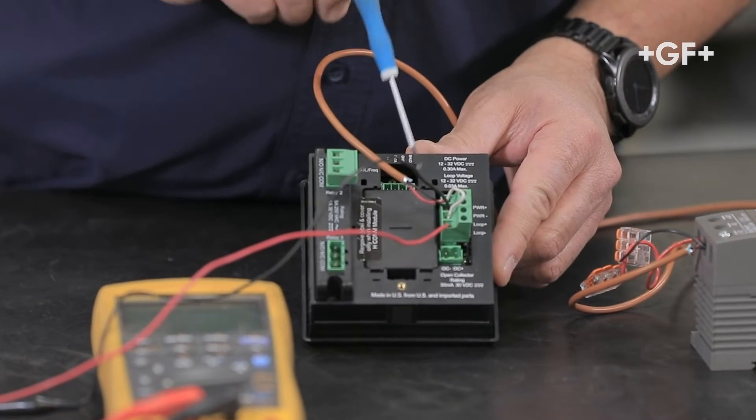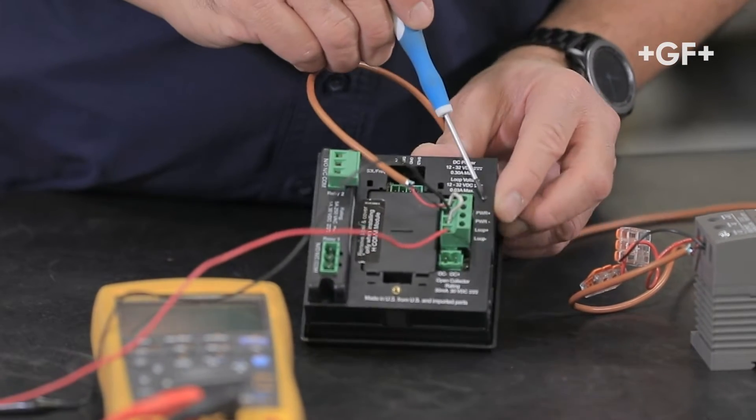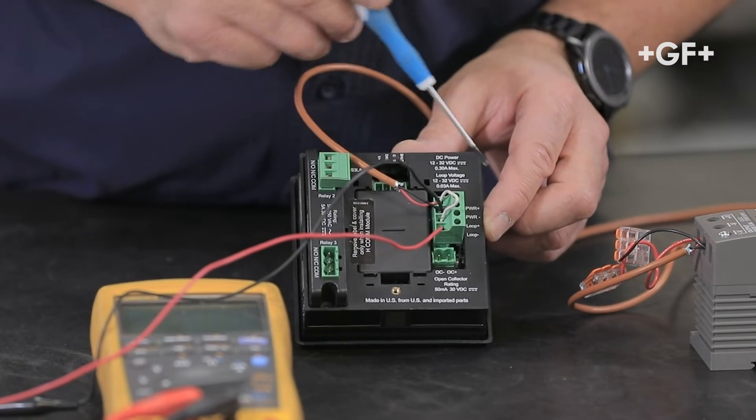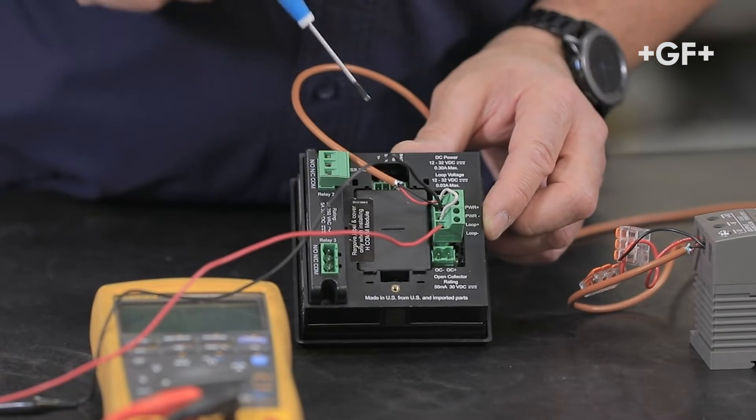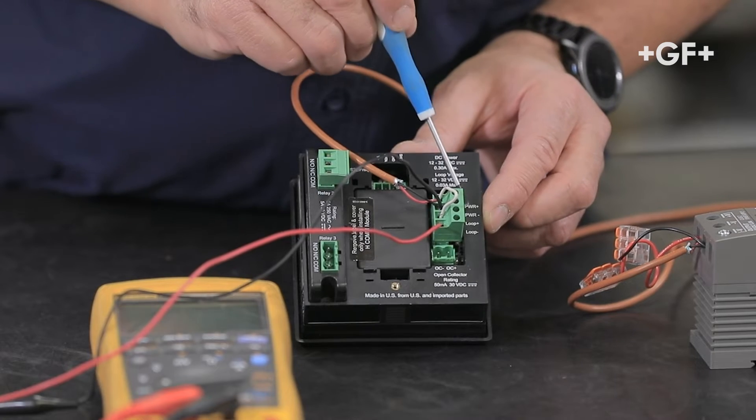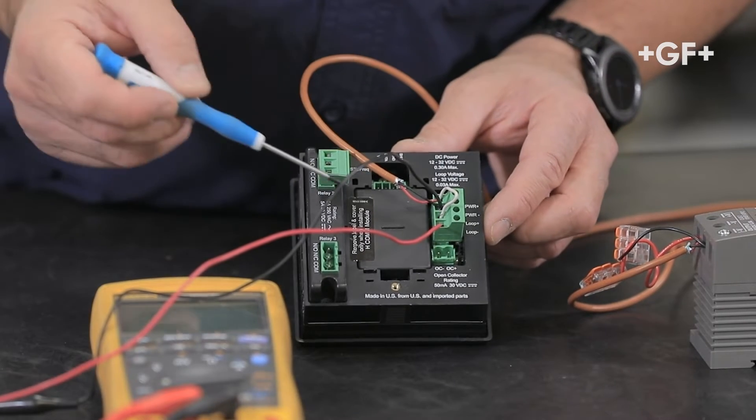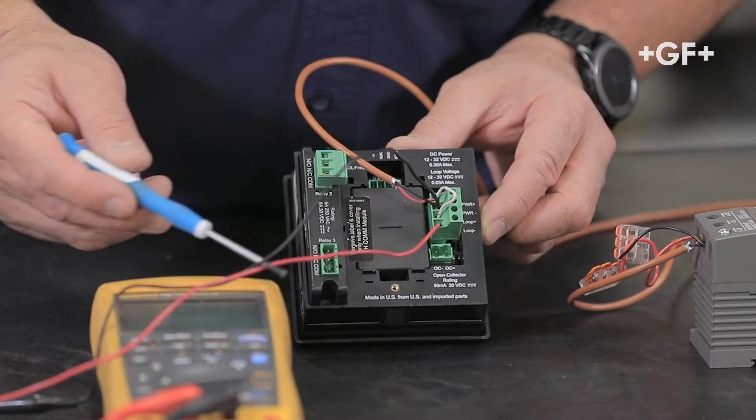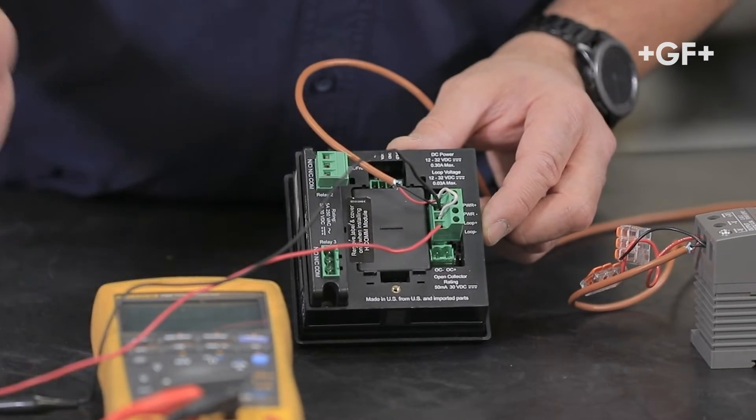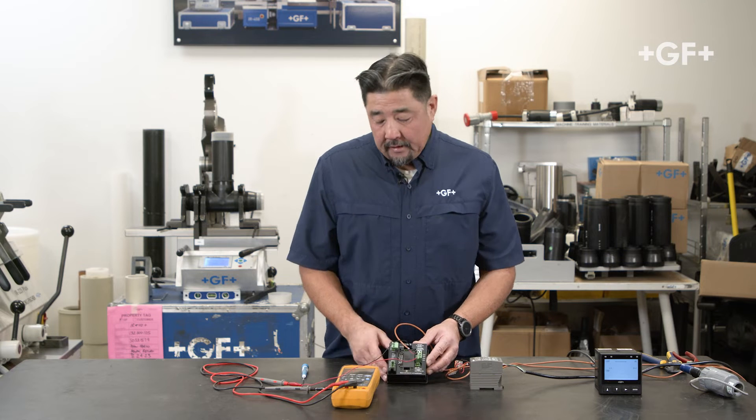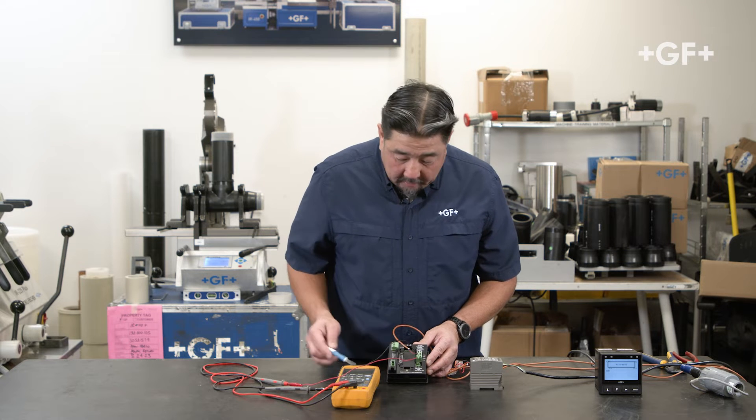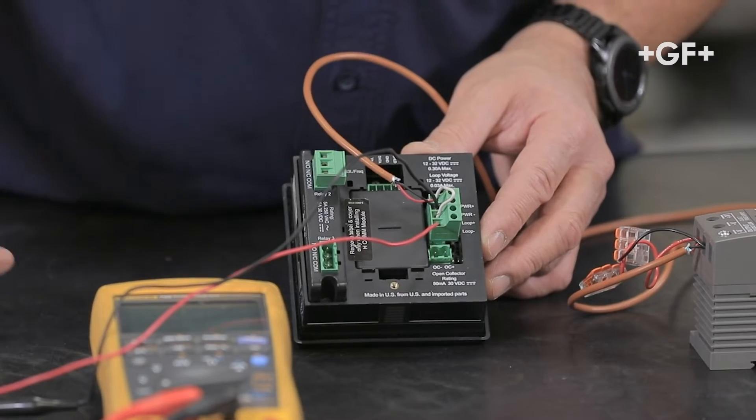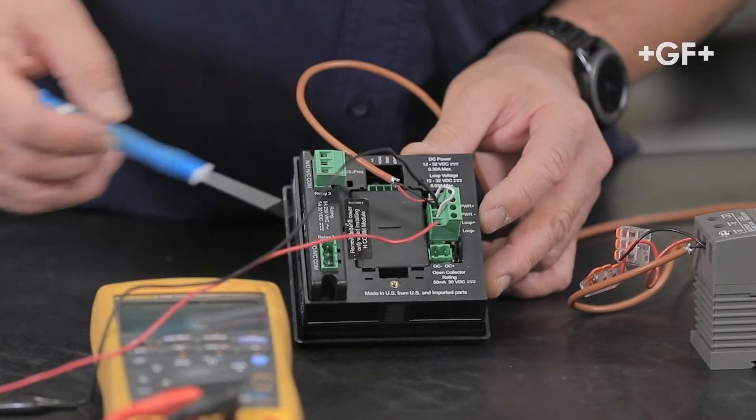24 volt positive coming into power plus, it's jumpered over to loop plus. I have zero volts to power minus. And as my signal lead I have that wired into loop minus going into the multimeter. This could be a chemical feed pump, chart recorder, data logger, any of those other 4-20 data collection devices. And then I have the ground ran back to power minus.